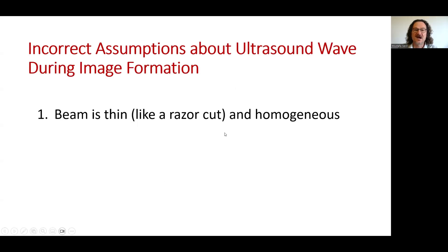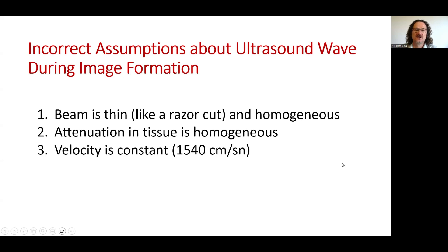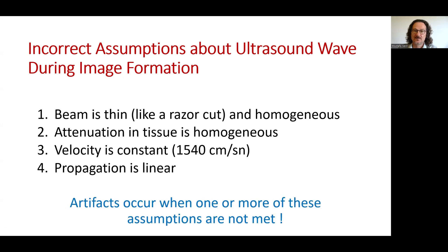The device assumes that the beam is thin and homogeneous, attenuation in the tissue is homogeneous, the velocity is constant, and the propagation is linear. Artifacts occur when one or more of these assumptions do not hold.